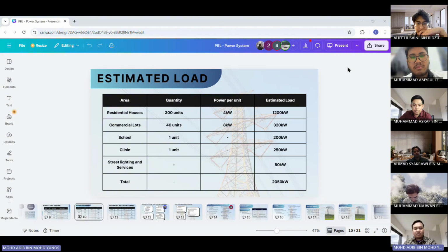All right. So we will start with the estimated load. As we can see, if every single light, AC unit and machine in this township were switched on simultaneously, our total load would be 2050 kilowatt. The heavy hitters here: 1,200 kilowatt coming from the 300 residential units, and a significant 250 kilowatt dedicated strictly to the clinic.